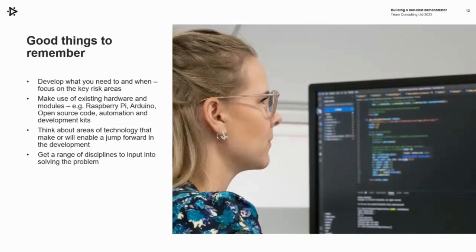An example might be a new fluidic cartridge with a clever chip to detect a key analyte, but moving the fluid to the chip might not have been done. There's lots of different example products doing exactly that, suggesting that that's a mature technology, but the detection method itself might be very novel and still needs proving. So that suggests that's where early development efforts should be focused, and demonstrators should be developed accordingly. And at some point in the future, the transfer of fluid might be included in those demonstrators.